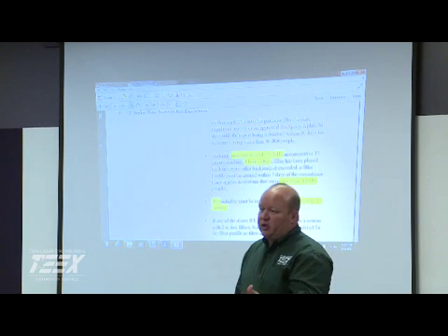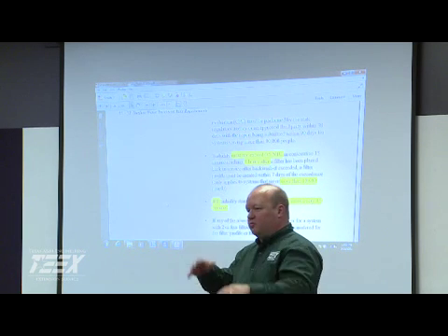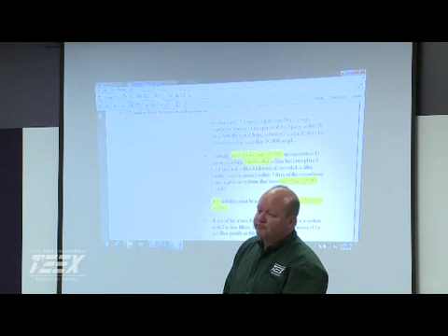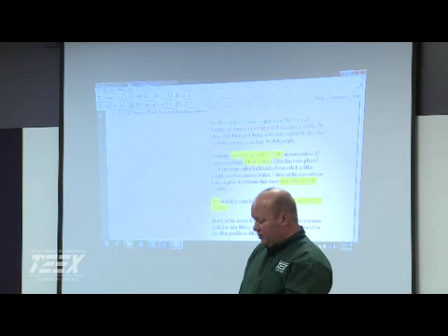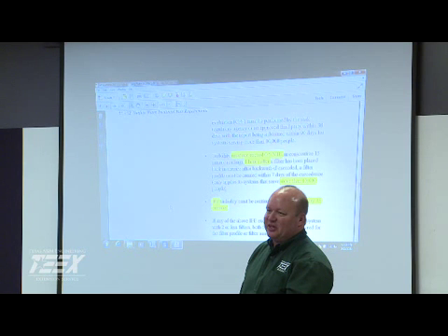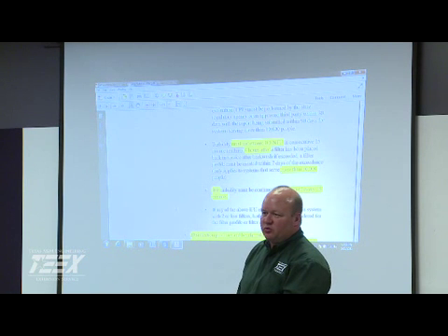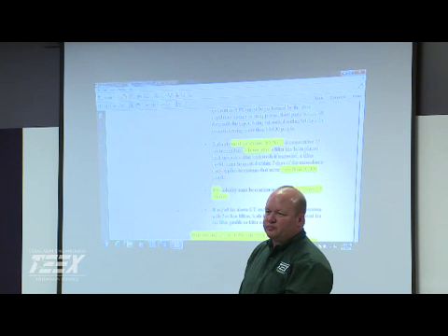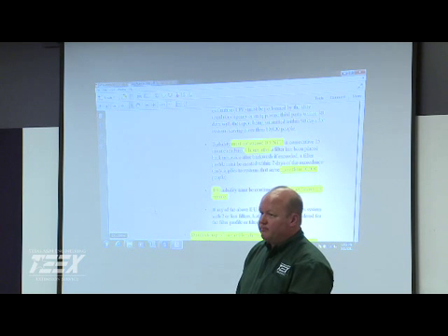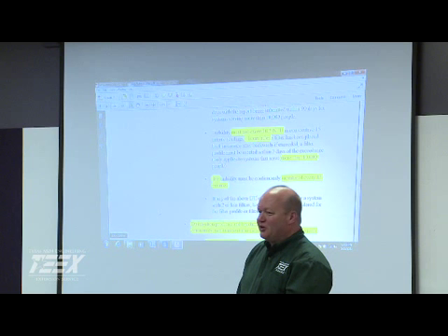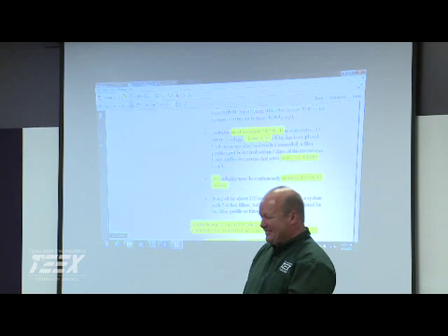But if you're getting enough in there that your differentials are changing, you figure out that different times of the year, your water quality is a lot different. What do y'all have the most issues with? Fall, springtime? Usually it's fall. That's when we start getting a lot more air binding and stuff like that in our filters. Good to know your plant, good to know your source.